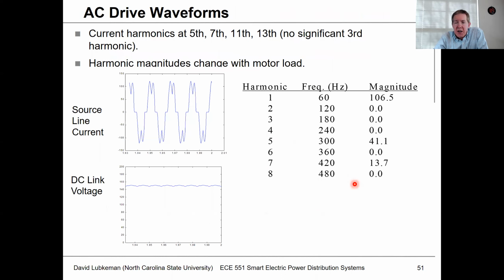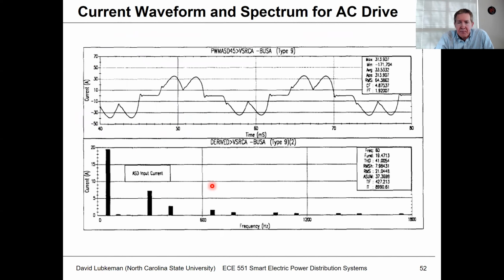If you look at the line input current, this gives you what we saw before. It gives you this particular characteristic with these particular harmonics. And of course, this is going to be a function of the load. The link DC voltage is constant for the most part. There's a little bit of a ripple on it.